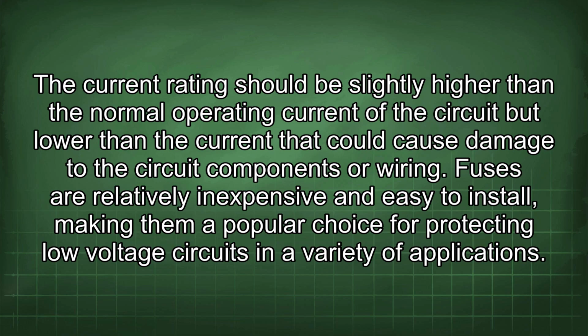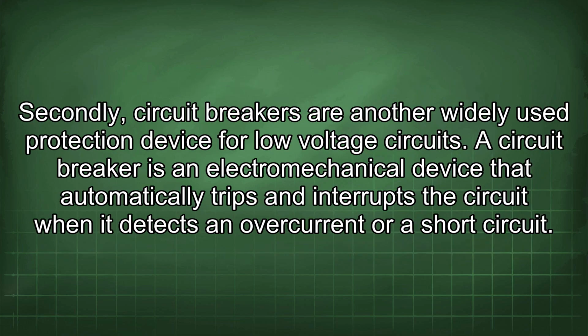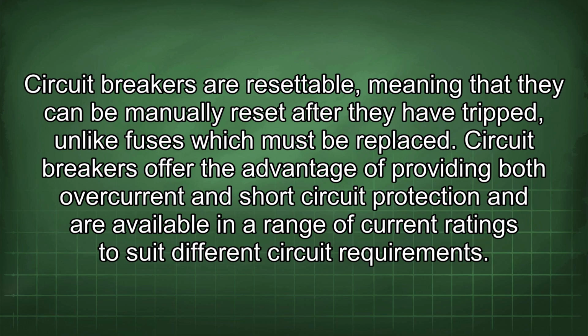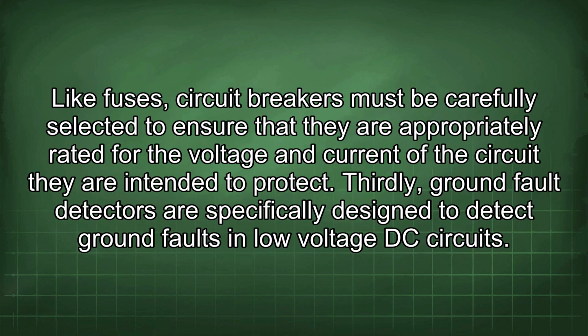Fuses are relatively inexpensive and easy to install, making them a popular choice for protecting low-voltage circuits in a variety of applications. Secondly, circuit breakers are another widely used protection device for low-voltage circuits. A circuit breaker is an electromechanical device that automatically trips and interrupts the circuit when it detects an overcurrent or a short circuit. Circuit breakers are resettable, meaning that they can be manually reset after they have tripped, unlike fuses which must be replaced. Circuit breakers offer the advantage of providing both overcurrent and short circuit protection and are available in a range of current ratings to suit different circuit requirements. Like fuses, circuit breakers must be carefully selected to ensure that they are appropriately rated for the voltage and current of the circuit they are intended to protect.